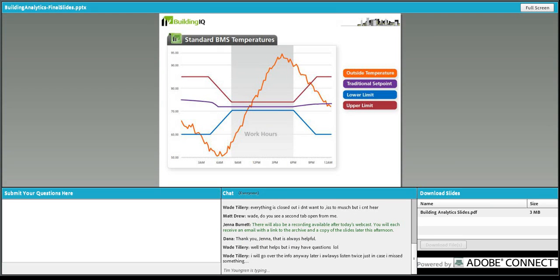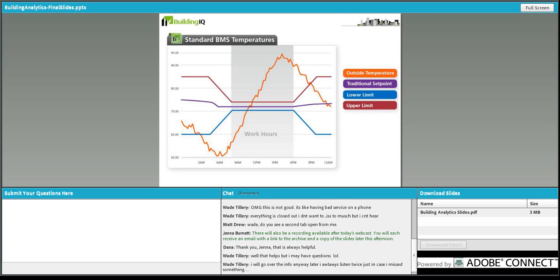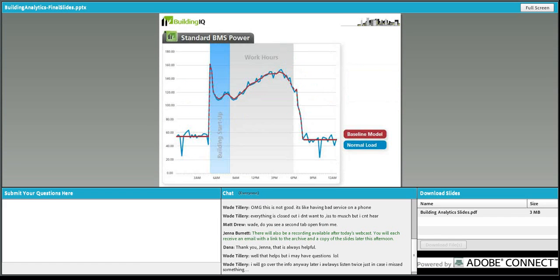I'll continue on. So the set point in a traditional building is held steady throughout the day. From whenever the plant comes on, it's working to maintain a certain set point between some limits—there might be deadbands or the like—and we see the ambient temperature there. The important thing about the BuildingIQ approach is taking all that subtlety, everything that goes into maintaining that temperature, and translating it into a power profile. So if we look at a standard way a building might be operated, we have that startup peak, then ramping through the day to maintain that set point.